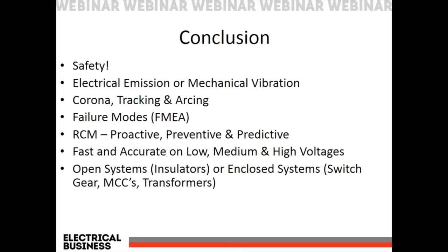Ultrasound is very fast and accurate on all voltages, and it can be used on all different types of systems, open systems or enclosed systems. And we do not, and I would repeat this, we do not have to open up the panel to determine what is going on behind it if there is an electrical emission.